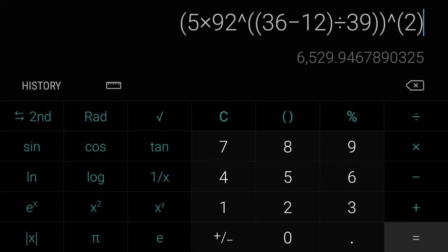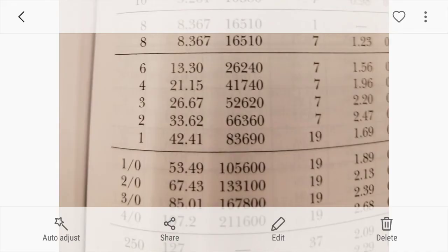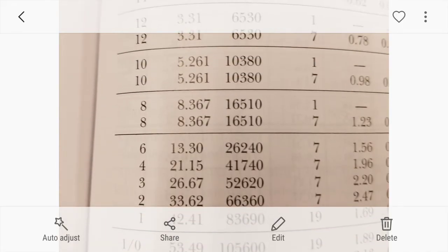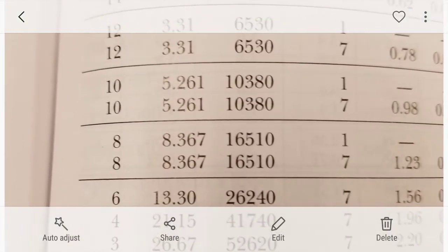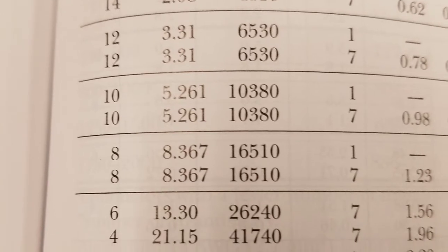And then close out the very first parenthesis and hit square. And now you have 6,529 circular mils, which if you round up that would be 6,530 circular mils.